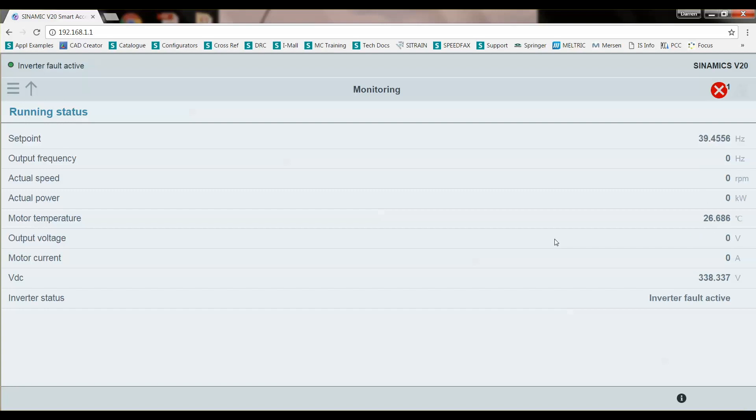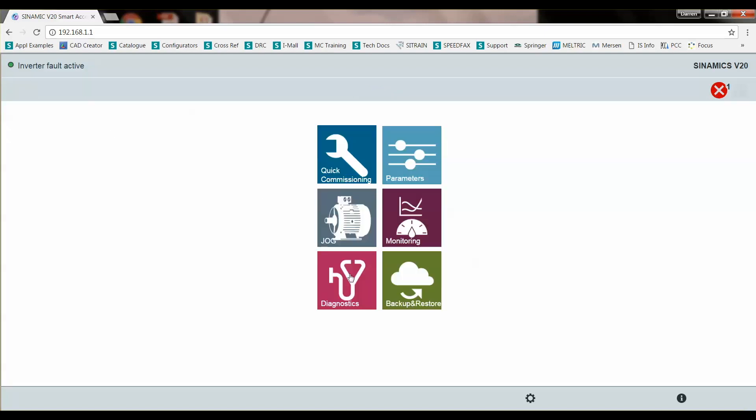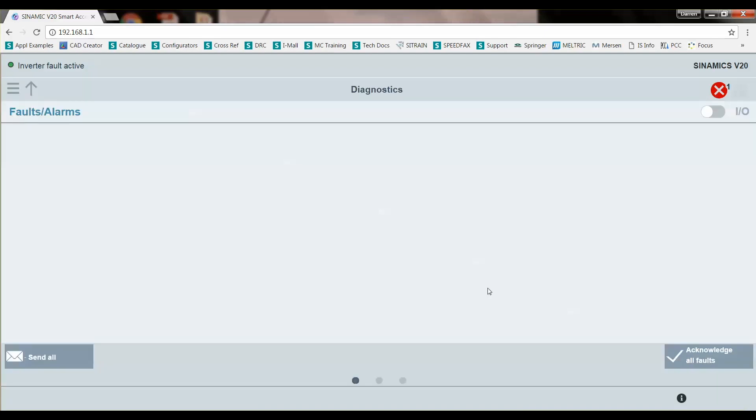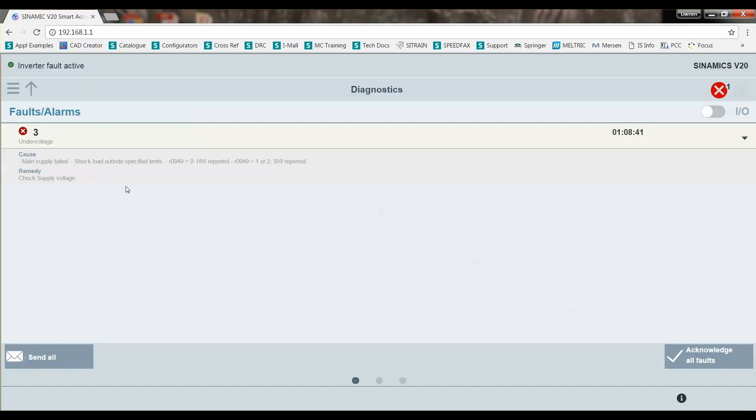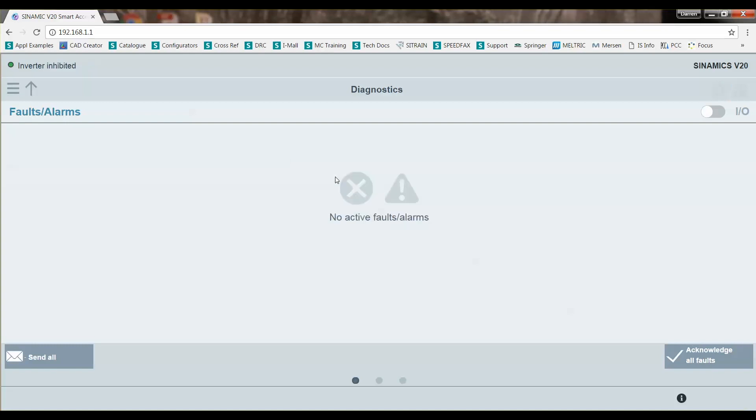You can see that this little indicator shows I have a fault. I can click on that indicator or I can go to diagnostics, see my faults. I get an under voltage. Click on that. The cause, mains supply failed. Check the supply voltage. I know that's true, that was the issue. So I can acknowledge my faults here. So the fault's acknowledged. Now I'm ready to run again.